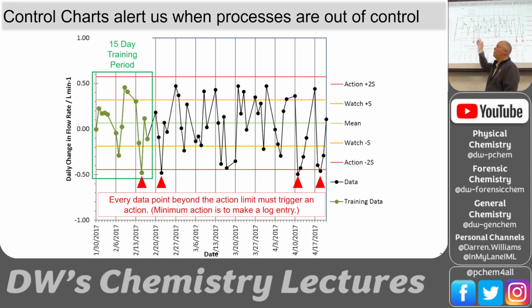But if it's in control, we don't have to do that, because it seems like nothing's changed. It's still behaving like it did historically, so we wouldn't waste all that time. But if it's off, then we know, well, I can't run these samples yet because something's wrong with my GC. So you've got to explore, reset the heat, reset the oven, and run your sample again. If it comes out in control, okay, then you can proceed with your work.